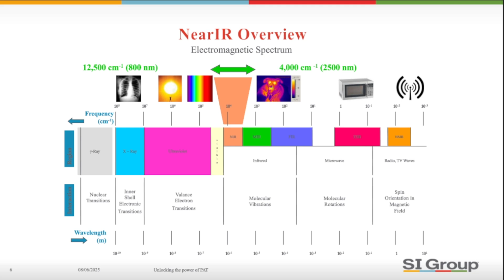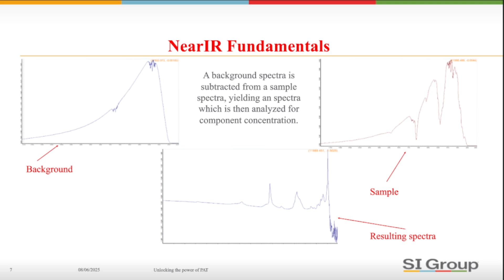Now, just a little information on how the software running the instrument works. A clean sample, a clean spectra is analyzed and recorded. This is taken without the probe being in contact with any chemical, simply light going through the fiber optic cable, through the probe, and back through the other fiber optic cable. This is a baseline or background. Once this is done, the probe is placed in reaction material. The second picture here is an example of a sample spectra. The baseline is then subtracted from the sample spectra to show absorbances over the spectral range. The third picture here is an example of this, and it is this spectra which is then analyzed and yields, for example, component concentrations.